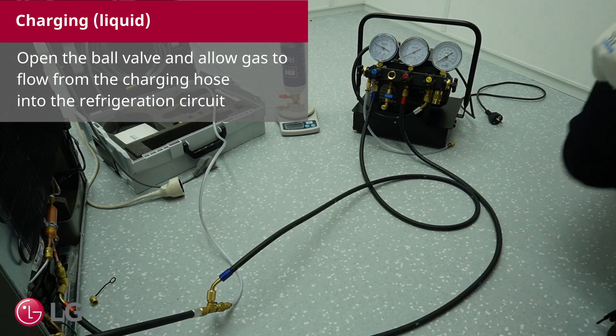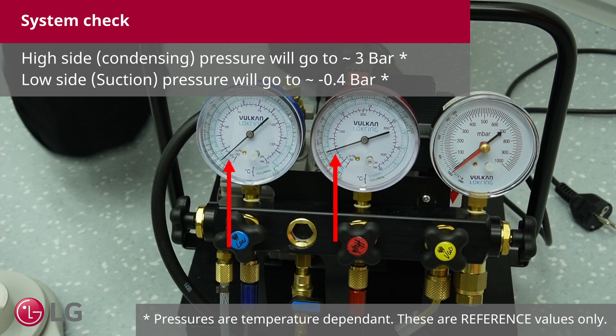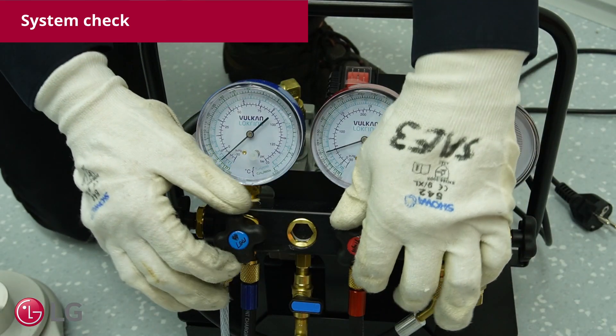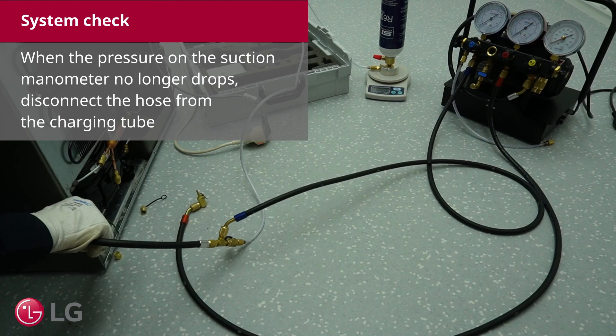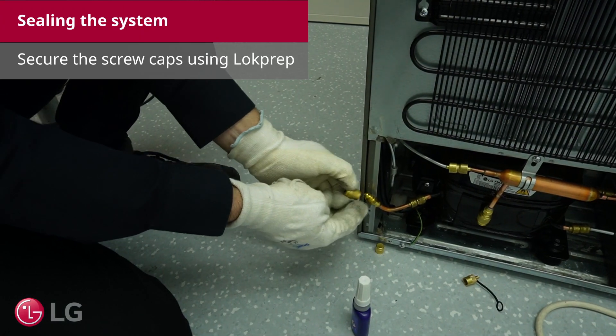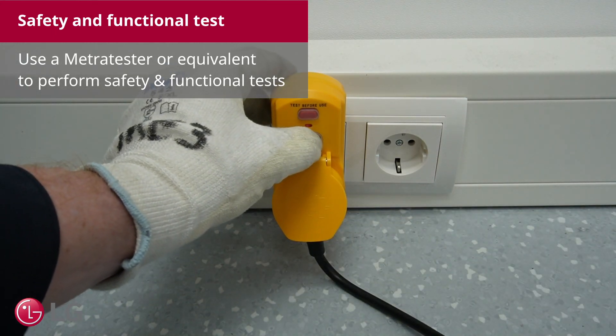Open the ball valve and allow gas to flow from the charging hose into the refrigeration circuit. Turn on the compressor. Check the suction and condensing pressures. The high side pressure will go to roughly 3 bar and the low side pressure to roughly -0.4 bar. The measured values highly depend on the ambient temperature. Disconnect the hose from the dryer. Open the pressure and suction valves — the pressure briefly rises and then drops to stable values. The system extracts refrigerant from the hoses. Wait a few minutes and watch the low pressure stabilize. When the pressure on the suction manometer no longer drops, disconnect the hose from the charging tube. Turn off the compressor. Secure the screw caps using Lokprep. Use a METRA tester or equivalent to perform safety and functional tests.